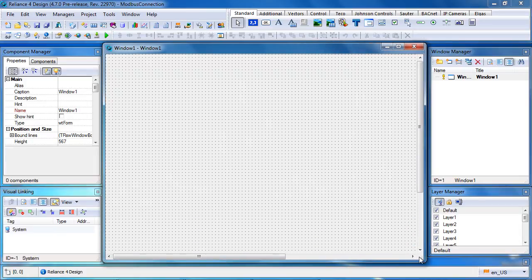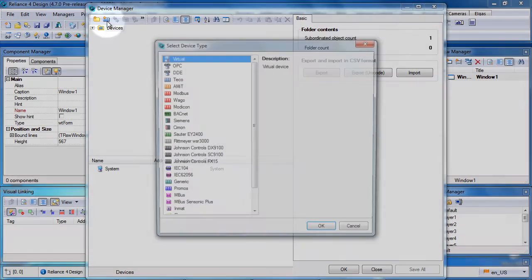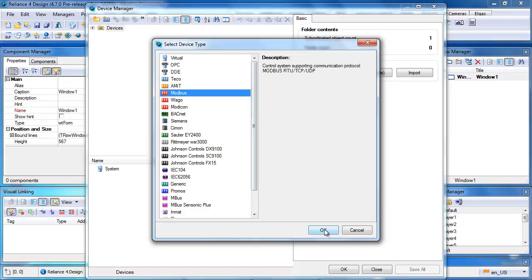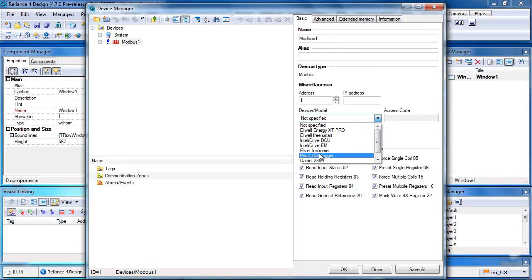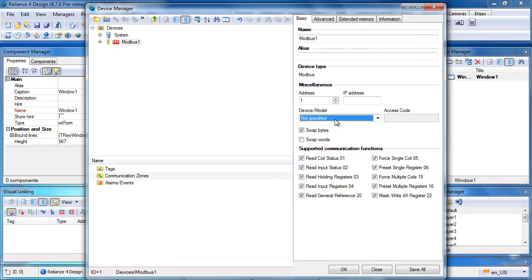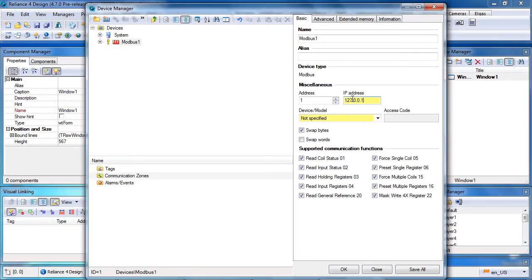Now, let's go to the Managers menu, open the device manager, click on New Device, and choose the Modbus device type. By default, this type of device allows connecting models communicating via the standard Modbus protocol. However, we can also choose one of the supported models that require special handling. In our example, a PLC communicating via the standard Modbus TCP protocol is connected, and here its IP address must be set. For the purpose of our example, we will be using a Modbus simulator running on the same computer, so the address is 127.0.0.1.